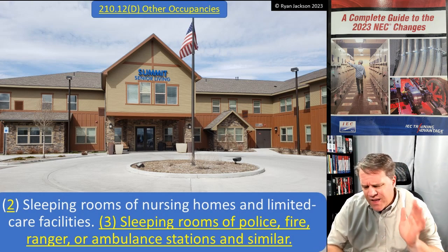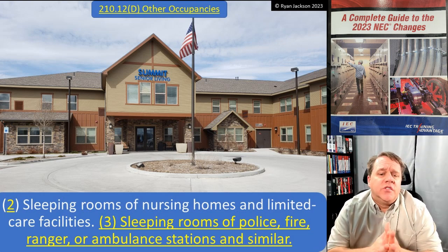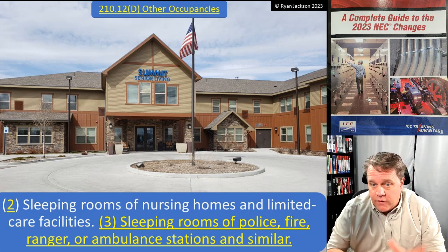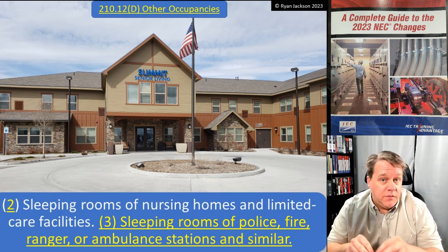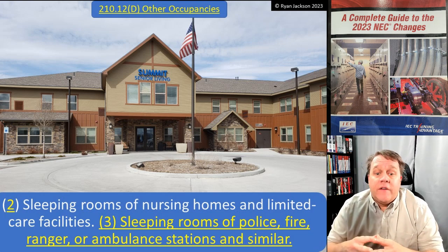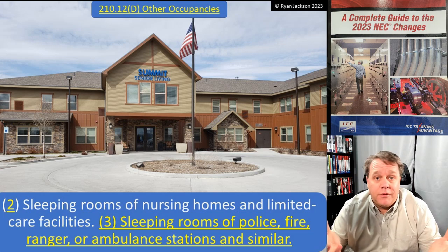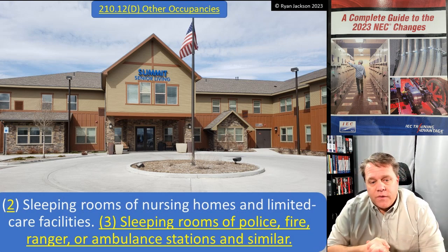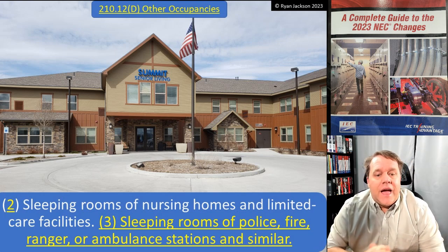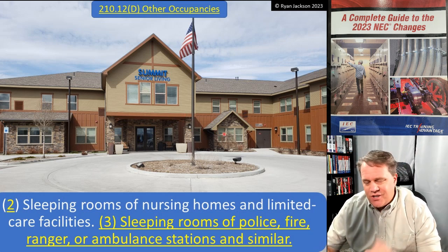For these facilities it's just the sleeping rooms. This is probably not a huge change because police stations, fire stations, and ambulance stations may already qualify as dormitory units depending on occupant count — if a fire station has more than 16 people sleeping there, it was already required. Police stations probably have fewer sleeping occupants, so that's more clearly new. Ranger stations are new. Ambulance stations too. So new requirements for AFCI protection, but nothing earth-shattering.